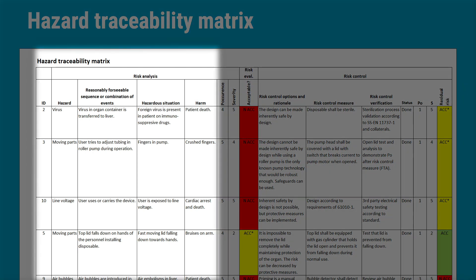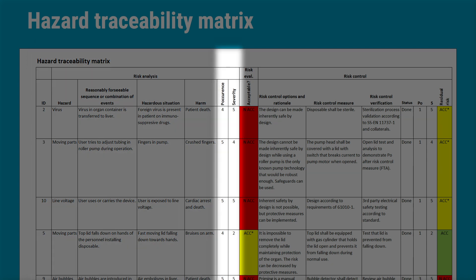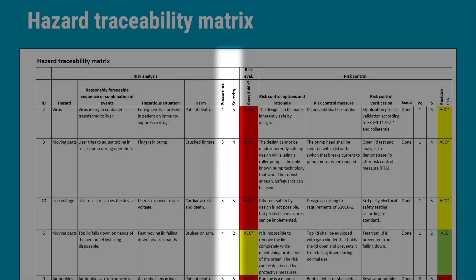If you look at the hazard traceability matrix as a reference of how far we've come in the process of risk analysis, you can see that we've gone through hazards, reasonably foreseeable sequences or combinations of events, hazardous situations, and harm. The only thing that remains in the risk analysis is to estimate the risk — estimating the probability of occurrence of the harm we previously defined and determining the severity of that harm.